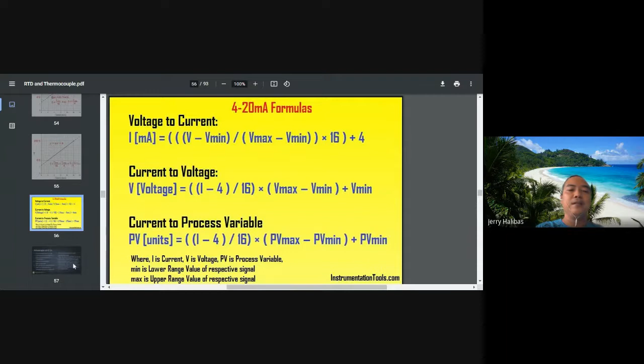But if the span does not start at 0, you can use this formula: the process value, let's say temperature, is equal to (current minus 4) divided by 16 times (the maximum process value or temperature minus the minimum temperature of the span), plus the minimum process value. Okay, you can memorize it if you like. So we go now to the advantages of RTD.